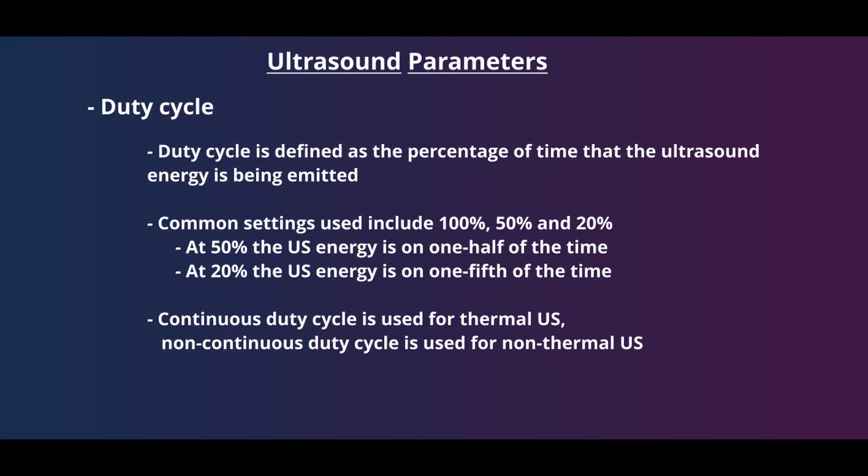Our next parameter is duty cycle, defined as the percentage of time that the ultrasound transducer is emitting energy. The duty cycle can range from 100% — a continuous ultrasound where it is always on — to 0% where ultrasound is off. Most units will have a few presets you can adjust. Using a lower duty cycle setting is a way to decrease the amount of energy being transmitted to the patient. As a general rule, continuous duty cycles of 100% are used for thermal ultrasound, while settings below that are used for non-thermal.